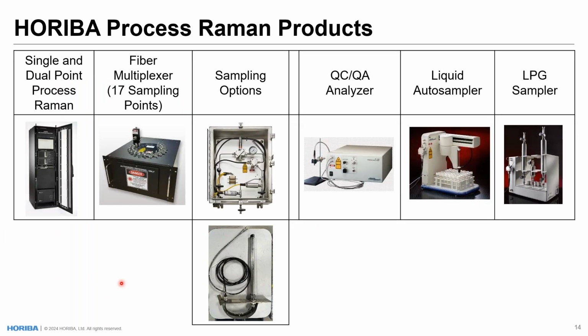So getting into the sort of Process Raman products that we offer with HORIBA. Over here on the left is sort of our flagship product. This is our single point process Raman system, as well as our dual point process Raman system. And if an end user is interested in looking at 3 to 17 sampling points, we can interface the single point process Raman unit with a fiber multiplexer, which allows for up to 17 sampling points with just one analyzer. So this is very useful for large-scale manufacturing operations and also to reduce capital costs overall.